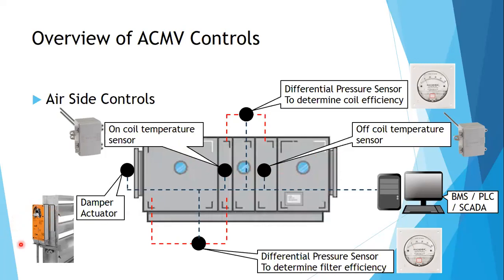And of course, you have your damper actuator. This damper actuator usually is hardwired to your air handling unit. It will tell your air handling unit, and your BMS, if it's closed or open. Because when the air handling unit is turned off, this actuator is usually also closed. When it's turned on, this actuator will open up. So this is on the operation of the air handling unit. When this actuator is closed, the unit is off, and when the unit is on, the actuator will open up.